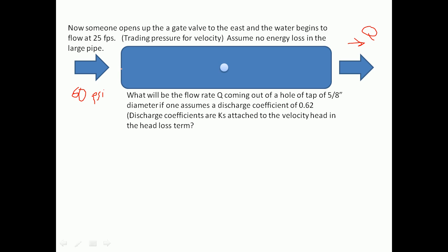Once again, knowing that your elevations are the same here. So what you had to start is you had 60 PSI, you had an initial pressure head of 60 PSI, which became PSF by 144 square inches over square feet. And that got you PSF. A PSF of your pressure PSF is something like 8640. Don't get used to always using the calculator convert program. Be able to convert pounds per square inch to pounds per square foot, and even more importantly, be able to convert 60 PSI to feet of water.